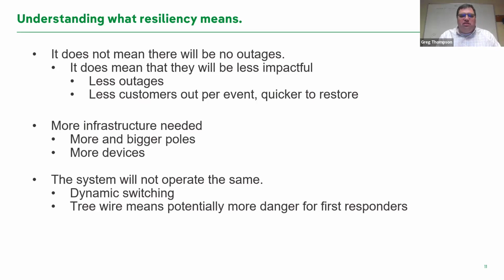Now, when you talk about this resiliency, tree wire, and all these reclosers, you have to start talking about the rest of the infrastructure. So now you're talking more poles, bigger poles, going to that class 5. In the old days we could run a smaller wire without any tree wire coating at probably 250-foot spans. Because of the tree wire and the weight, we might have to do 150-foot spans, so now you've added poles along the side of the road, which is a give and a take.